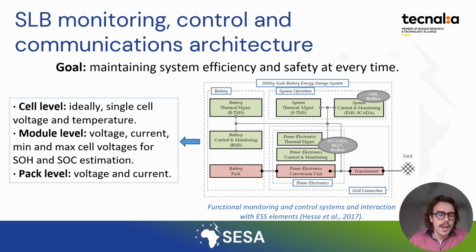Lastly, we have the battery pack level, which is the higher level of the BMS, where voltage and current are measured. As we can see in the figure 1, we see that the BMS interacts with higher level monitoring and control systems like the energy management system or EMS, the thermal management system or TMS, and the power electronics that are connected to this battery, and also the fire suppression system in charge of avoiding hazardous situations like fire.